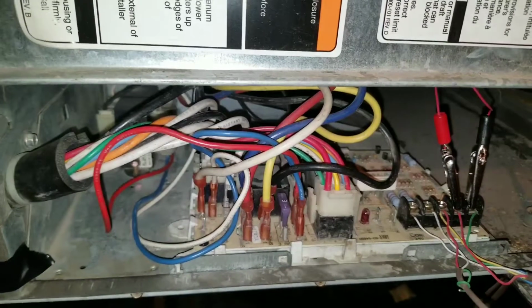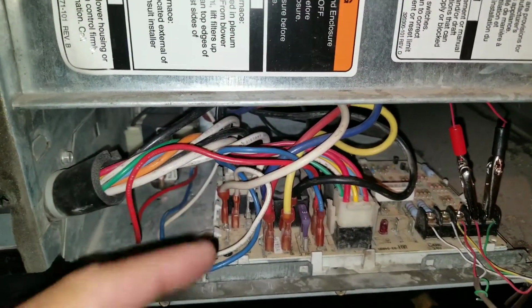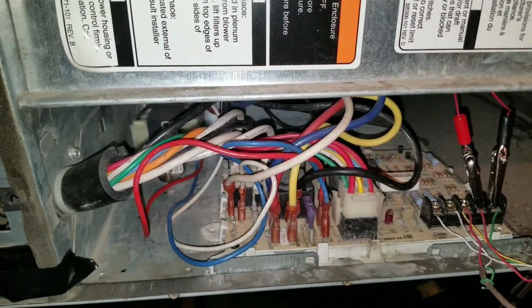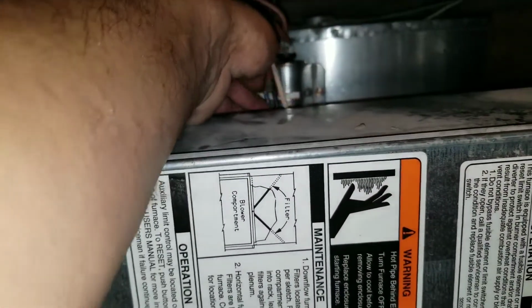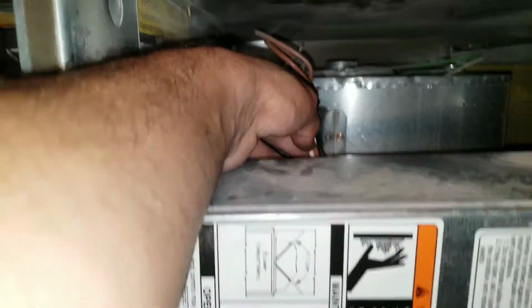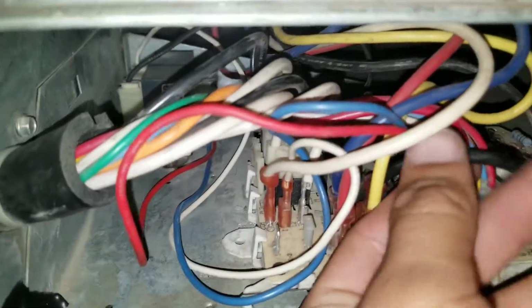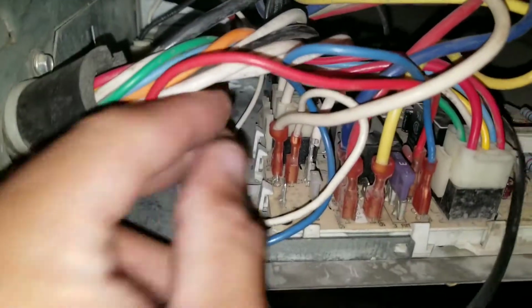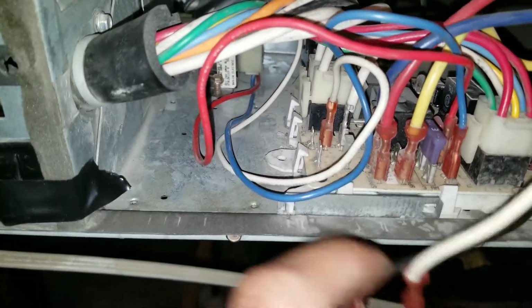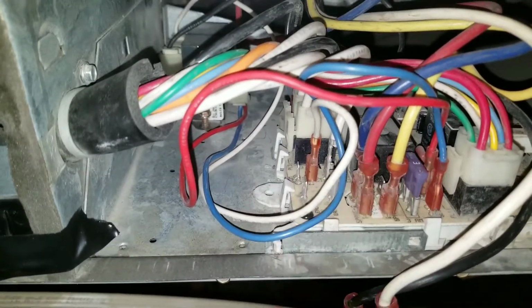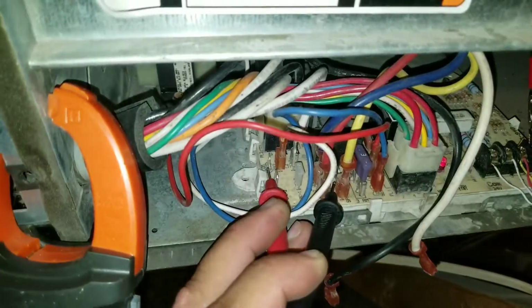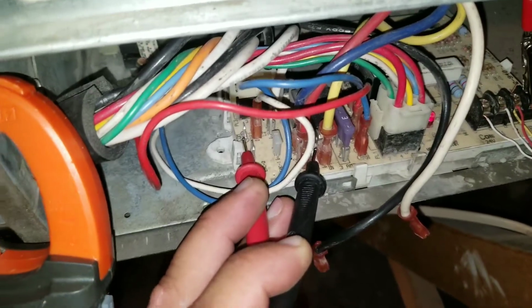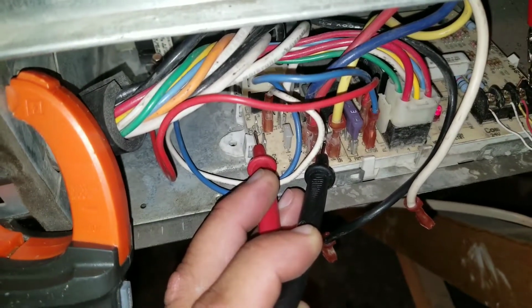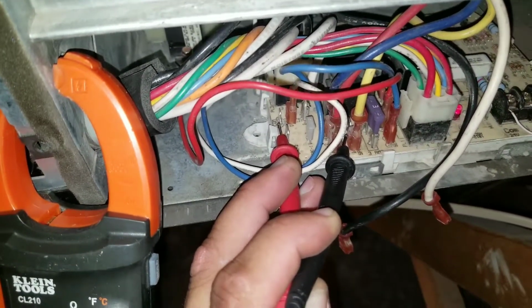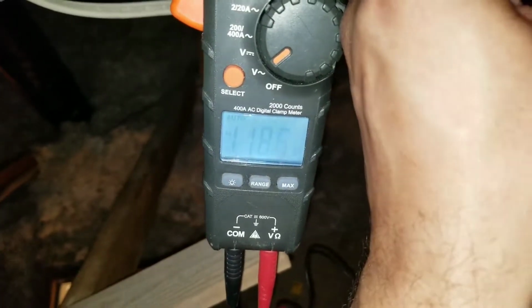This would also allow me to test my terminals here at the furnace board. So here I have my 2 wires coming from my blower motor to my furnace board. If I remove those wires, that would allow me to test for 120 volts at the furnace board. Here I remove my wires. I have my multimeter tapping each lead coming off the furnace board where my blower motor was tied in, and you can see here that I have a reading of 120 volts.